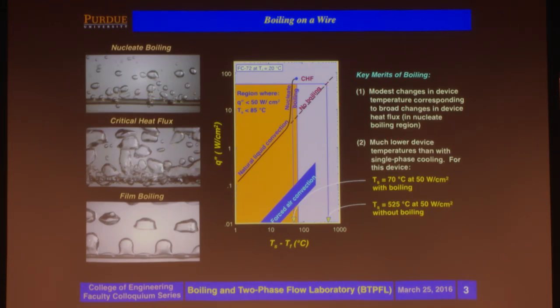So if you are able to find a fluid with a boiling point about 30 degrees below the maximum temperature, you see this large change in slope taking place right here. That allows you to maintain the surface temperature below 70 at the maximum flux, significantly less than the 525. Not only that, there is another advantage, and that is the slope itself.